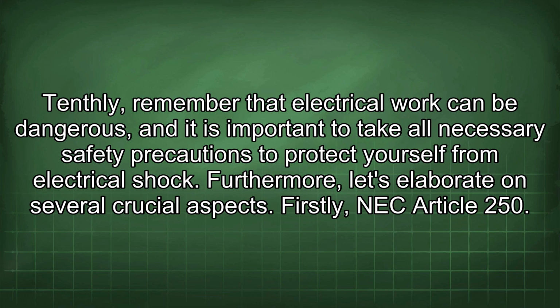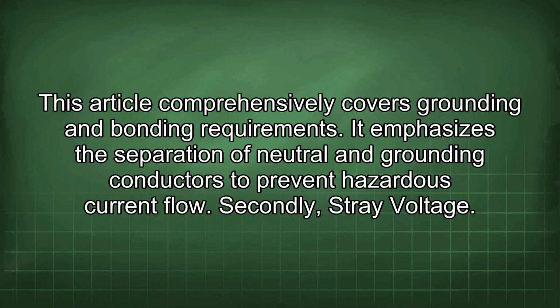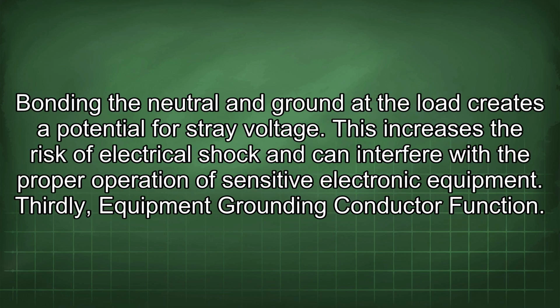Firstly, NEC Article 250. This article comprehensively covers grounding and bonding requirements. It emphasizes the separation of neutral and grounding conductors to prevent hazardous current flow. Secondly, stray voltage. Bonding the neutral and ground at the load creates a potential for stray voltage. This increases the risk of electrical shock and can interfere with the proper operation of sensitive electronic equipment.